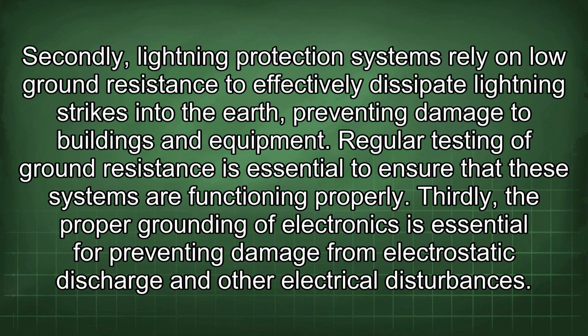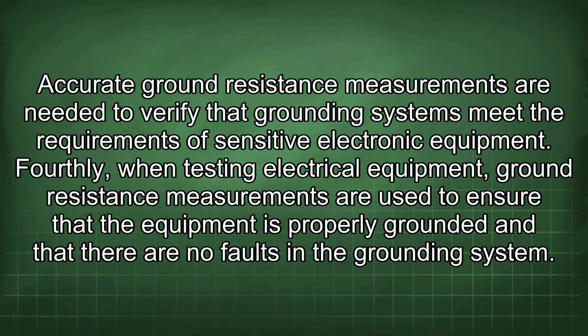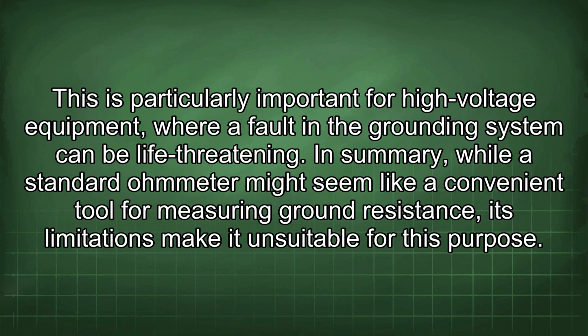Regular testing of ground resistance is essential to ensure that these systems are functioning properly. Thirdly, the proper grounding of electronics is essential for preventing damage from electrostatic discharge and other electrical disturbances. Accurate ground resistance measurements are needed to verify that grounding systems meet the requirements of sensitive electronic equipment. Fourthly, when testing electrical equipment, ground resistance measurements are used to ensure that the equipment is properly grounded and that there are no faults in the grounding system. This is particularly important for high-voltage equipment, where a fault in the grounding system can be life-threatening.